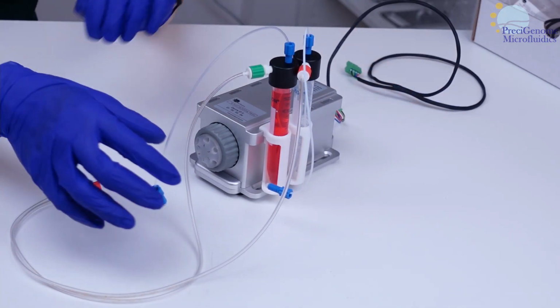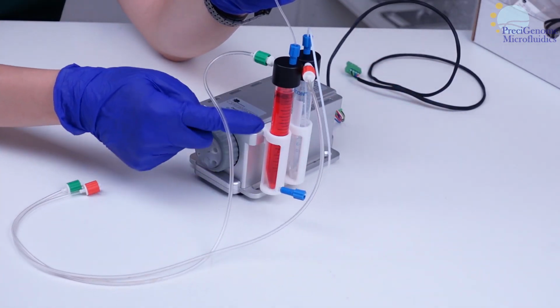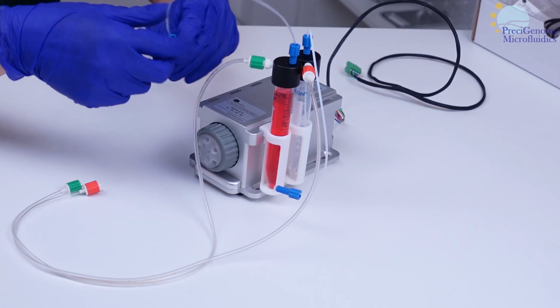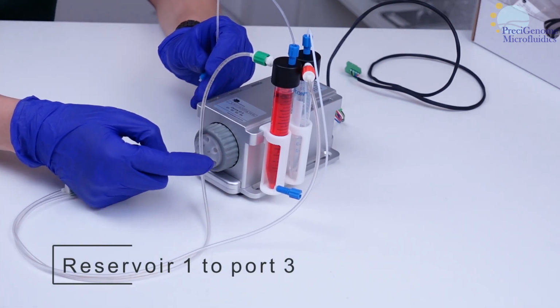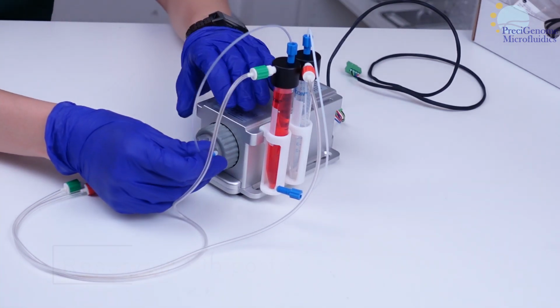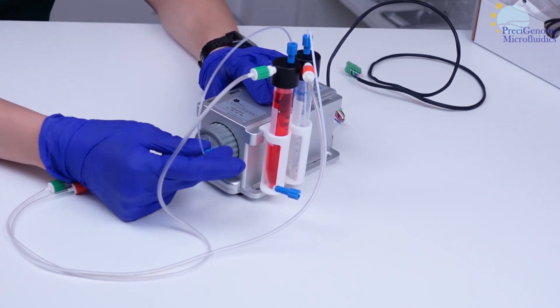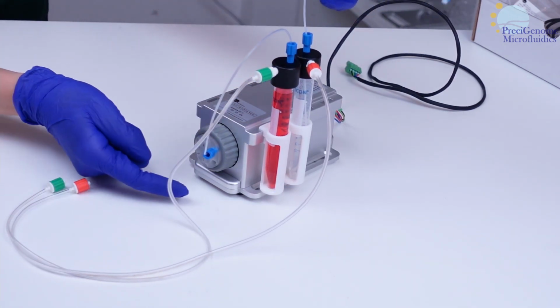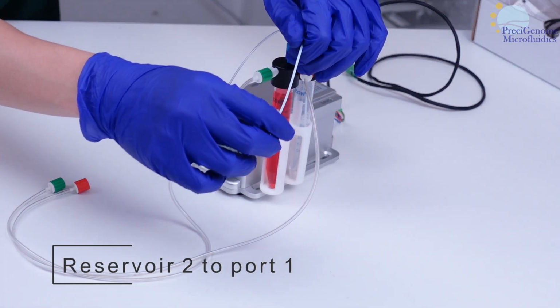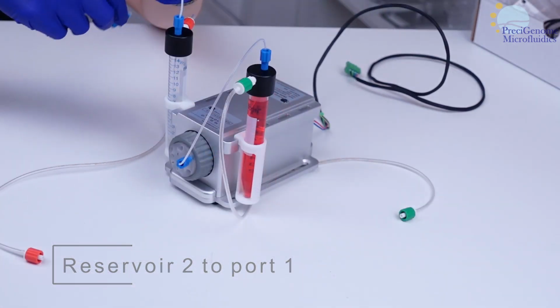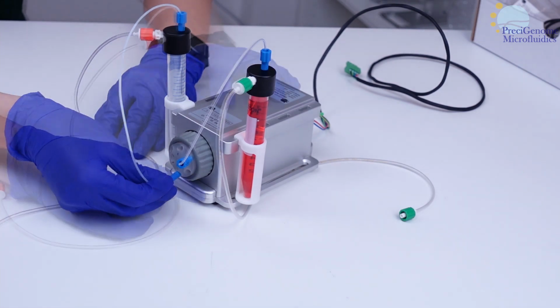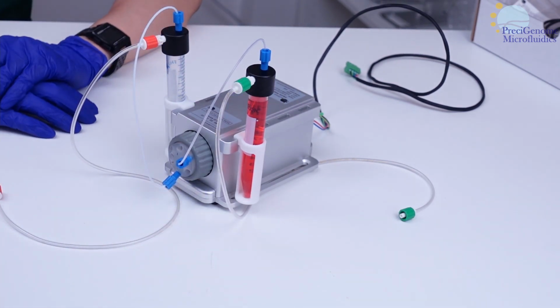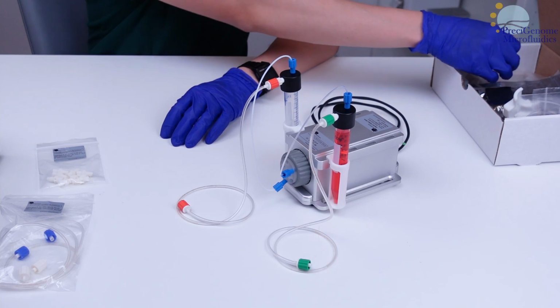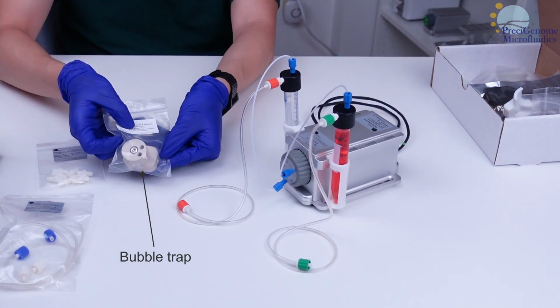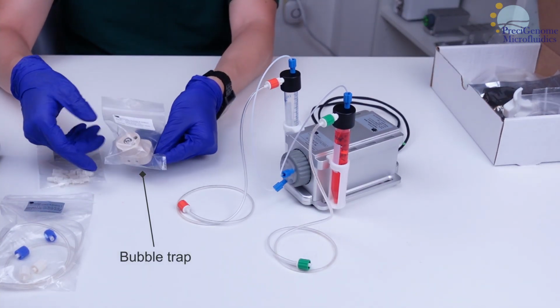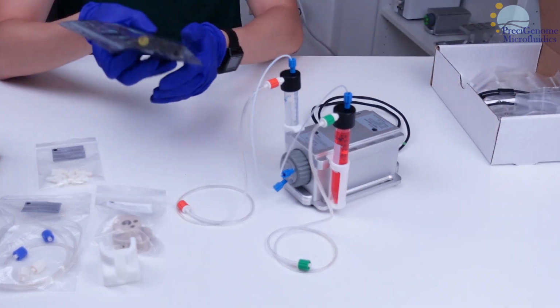We can now connect these reservoirs to the rotary valve with PTFE tubing. Start with Reservoir 1 and connect it to port 3. Next, connect Reservoir 2 to port 1. Now we'll need a bubble trap, and a flow sensor.